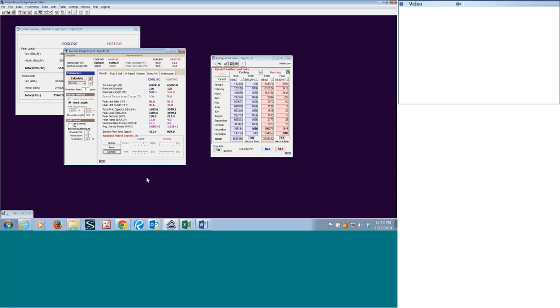Well, what we found, and this is really common, I'd say well over 50% of the jobs we see, is outside air being brought in through an economizer when it should be going through the ERV component. So middle of February in central Wyoming, outside air temperatures of 0 and 5 below 0 and even colder, and they're bringing in cold outside air 24/7, and I was amazed the loop field was staying as warm as it was. But we've also seen residential type heat pumps with strip heaters in them, and where we've seen the control sequence for heating.